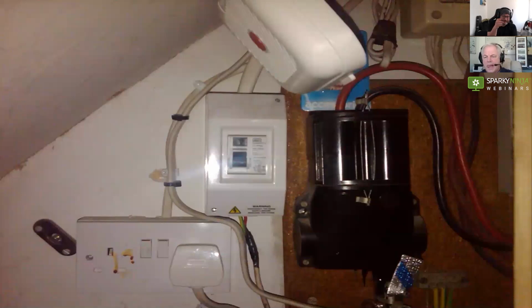If you've got access to a single insulated live conductor - it also depends how big the hole is that it's going into, the ingress. If you can stick your finger up inside that, then it becomes a C1. So there's not much good about that installation, really. But I've just noticed the cable going to the top looks a lot bigger than the cable coming up the bottom - it's huge. I'm not sure what the overcurrent requirements are, but is that feeding a shower? I'm assuming so - it does look suspicious.